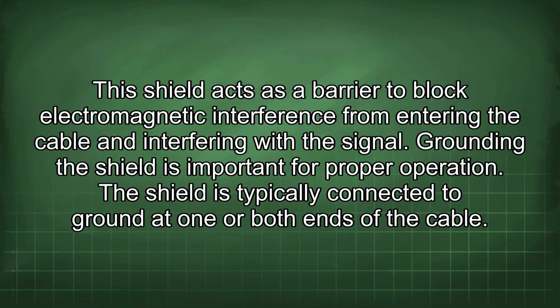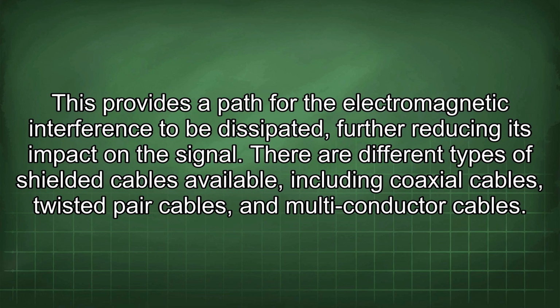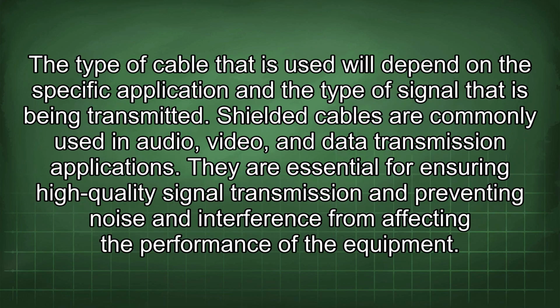Grounding the shield is important for proper operation. The shield is typically connected to ground at one or both ends of the cable. This provides a path for the electromagnetic interference to be dissipated, further reducing its impact on the signal. There are different types of shielded cables available, including coaxial cables, twisted pair cables, and multi-conductor cables. The type of cable that is used will depend on the specific application and the type of signal that is being transmitted. Shielded cables are commonly used in audio, video, and data transmission applications. They are essential for ensuring high-quality signal transmission and preventing noise and interference from affecting the performance of the equipment.